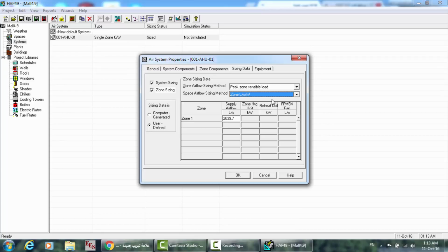The third is zone. Here the airflow will be calculated according to the peak zone sensible load of the zone, and then will be distributed on the spaces according to the liter per second per square meter. Okay, for this space. Now the schedule here, it's according to the system you have. It will be determined here if you can change many things or just this. Here is the supply airflow, liter per second. You can change it by yourself.